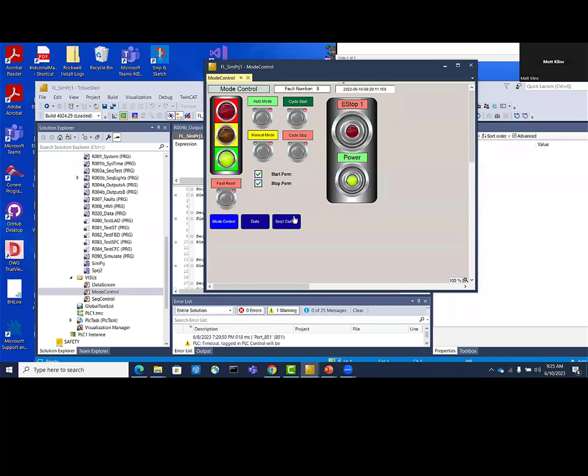Now, sometimes if I did something like a serious hardware change, I might have to do something like this, which is activate the configuration. That means I change something serious. When I do that, I'm doing the same thing as a download in the major PLC platforms. So I am going offline. I'm stopping the machine, disconnecting, basically, not running, downloading everything, making the change, and then going back online. So this is a little bit of the online view. And like I said, visualizations here, they work exactly like a regular HMI here.